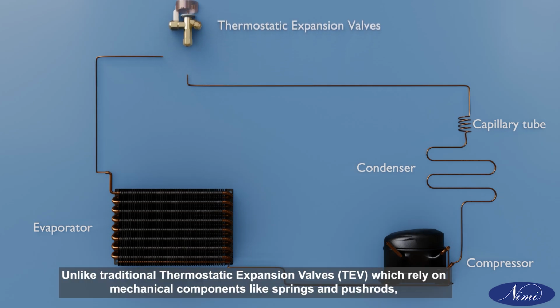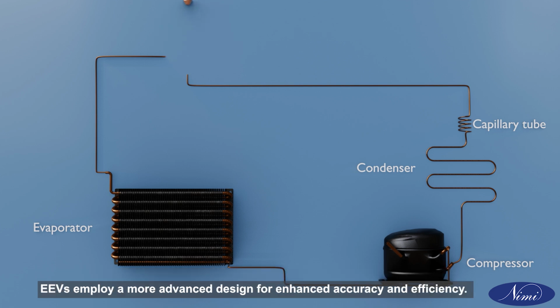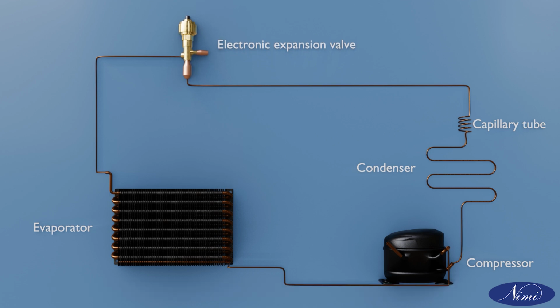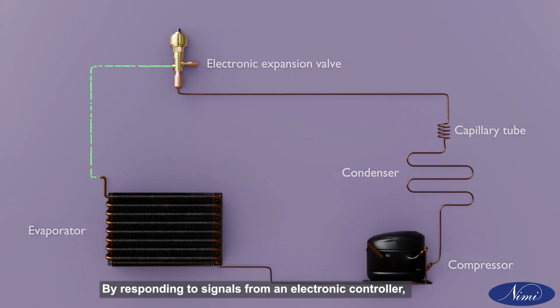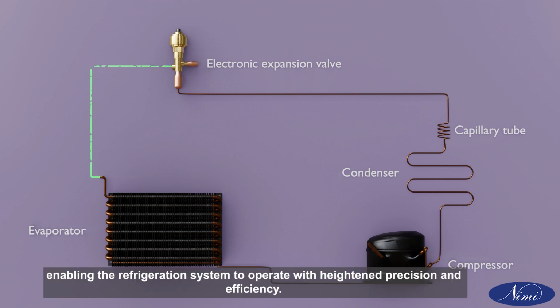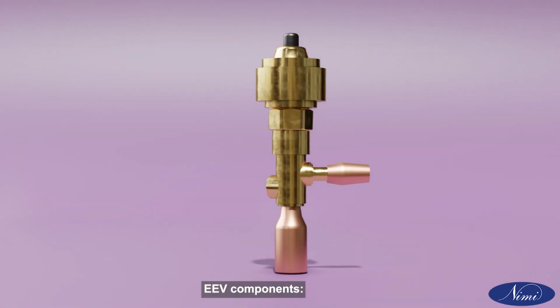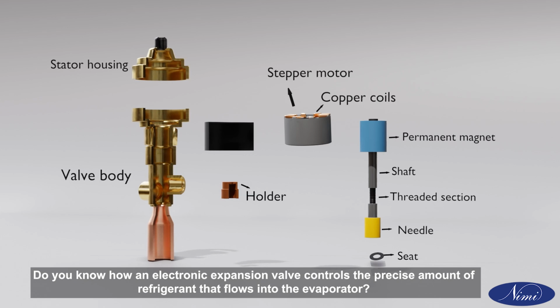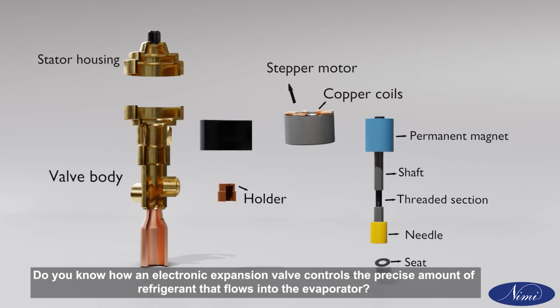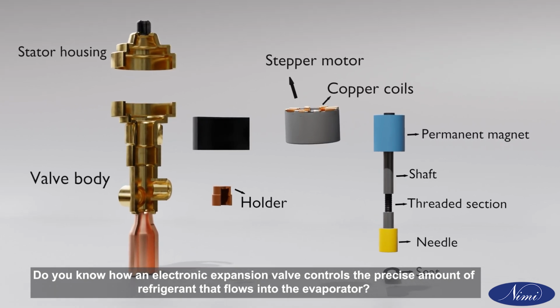Unlike traditional thermostatic expansion valves, TEV, which rely on mechanical components like springs and pushrods, EEVs employ a more advanced design for enhanced accuracy and efficiency. By responding to signals from an electronic controller, EEVs adjust the refrigerant flow into the evaporator, enabling the refrigeration system to operate with heightened precision and efficiency. EEV components.